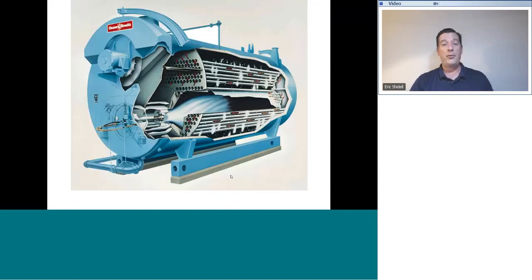Here's an example of what's called a fire tube boiler with a very large power burner on it. This power burner has a big blower up here, and it is blowing downward, taking air from the surrounding atmosphere, blowing it downward into the burner, through the burner tube. Meanwhile, fuel is injected along with that air. Remember, our fuel is delivered under pressure, but low pressure. So the delivery of this air can't be very high pressure either. Otherwise, we wouldn't be able to get any fuel to mix with it.